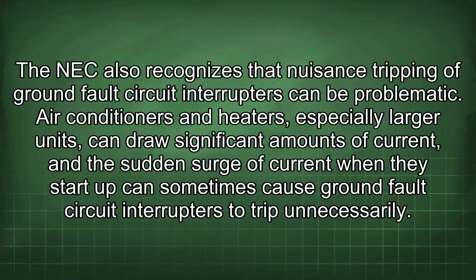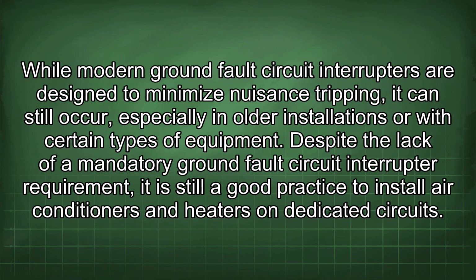The NEC also recognizes that nuisance tripping of ground fault circuit interrupters can be problematic. Air conditioners and heaters, especially larger units, can draw significant amounts of current, and the sudden surge of current when they start up can sometimes cause ground fault circuit interrupters to trip unnecessarily. While modern ground fault circuit interrupters are designed to minimize nuisance tripping, it can still occur, especially in older installations or with certain types of equipment.